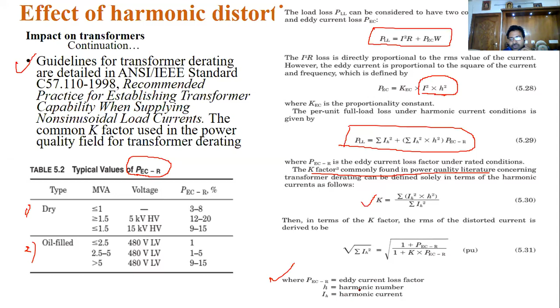Now calculate what is the K. K is the factor commonly found in power quality issues. Then K is calculated like this. H is the harmonic component value. Remember this one. You can calculate the PEC like this. What is the PEC value here? PEC is nothing but the eddy current loss factor. H is the harmonic component number, 1, 2, 3, 4, 5 and so on. IH is the harmonic current value.